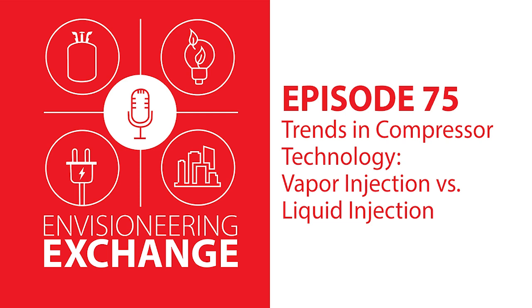And as you said, there's a lot of different types, right? There's water to air, so basically you're using air to cool water. There's air to air. So think of that as something like for a rooftop or a DOAS unit where you're bringing in maybe colder air to give the cooling system a break or introducing more fresh air into the system to increase the efficiency a little bit. So there's two types there, but really the type we're going to talk about today is the refrigerant side. So refrigerant coming in, refrigerant going out, and that's the portion of the economizer we're going to talk about today as it pertains to vapor injection specifically.